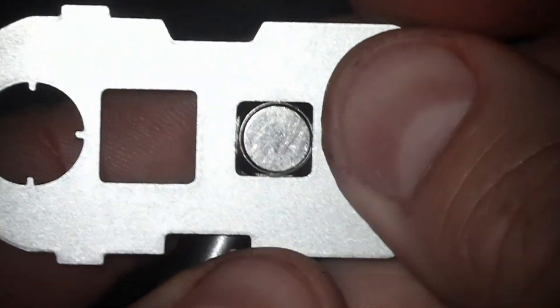Then remove the back cap by using the square wrench, and make sure to examine the back of the cap to make sure there's no debris inside there as well. Sometimes you'll need to use either a dummy burr or a big carbide to pop the turbine out. In this case, the turbine came out with the back cap.